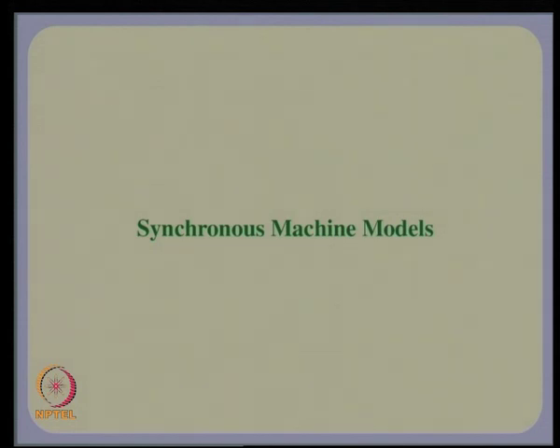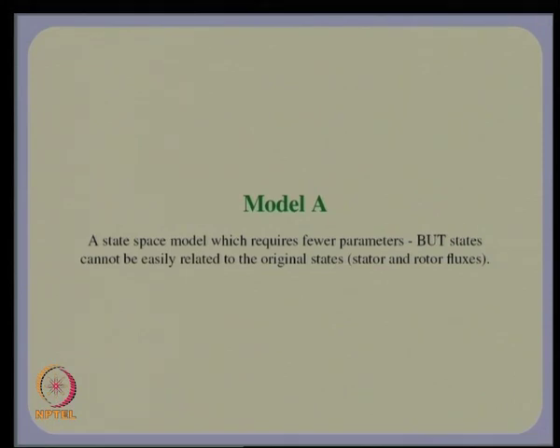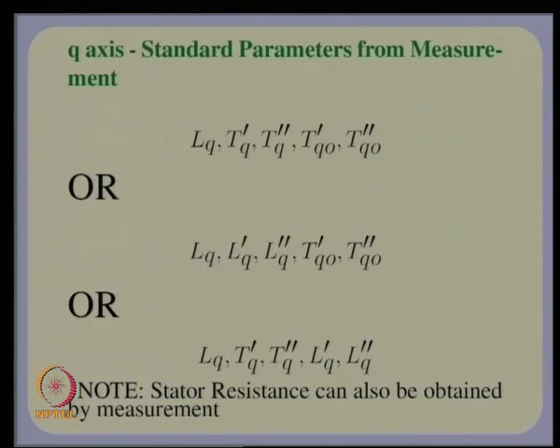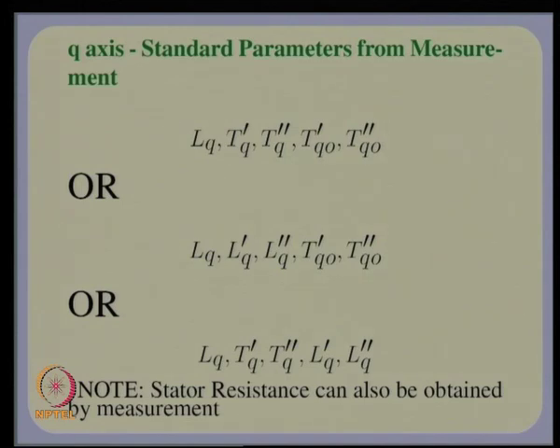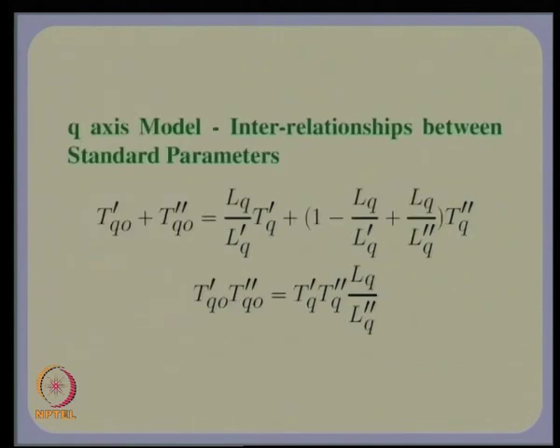Looking at the synchronous machine models — that is, the state space models — we discussed Model A, which requires fewer parameters. We use directly the standard parameters, but the states cannot be easily related to the original states, which are the stator and rotor fluxes. We do retain the stator d and q axis flux state variables, but the rotor flux variables are not retained in this model. On the q axis, the standard parameters from measurements may be specified in terms of four time constants and an inductance, or three inductances and two time constants. In any form you may get this data, the time constants and inductances are related by a certain relationship, so they can be interchangeably used.